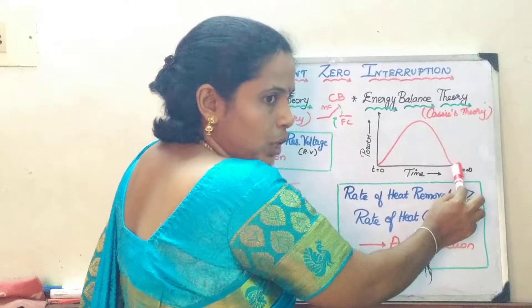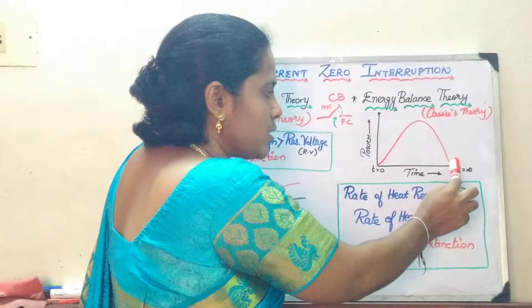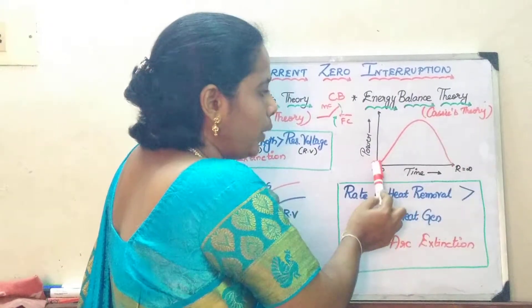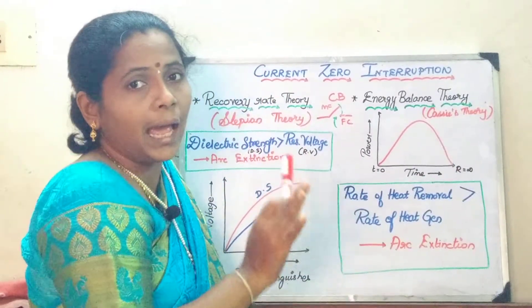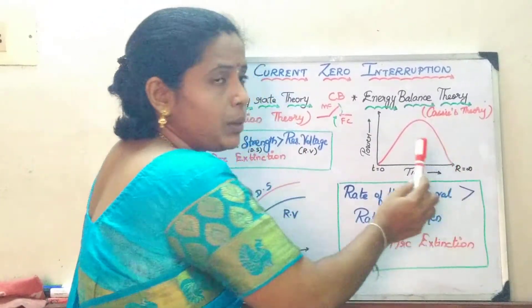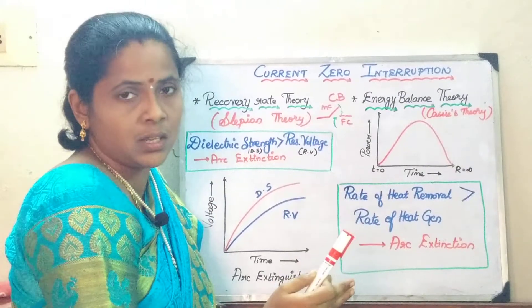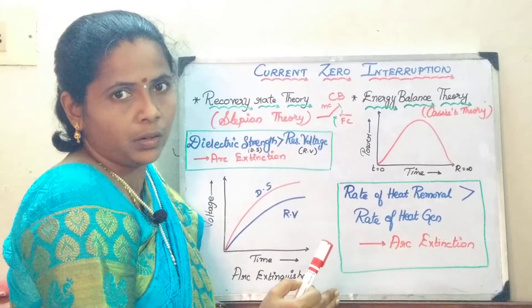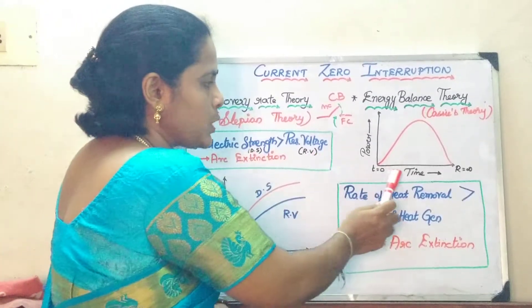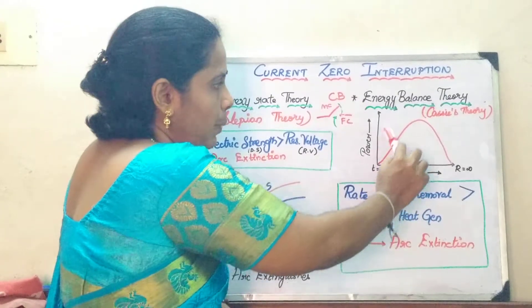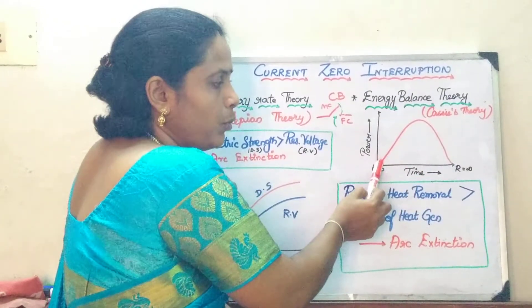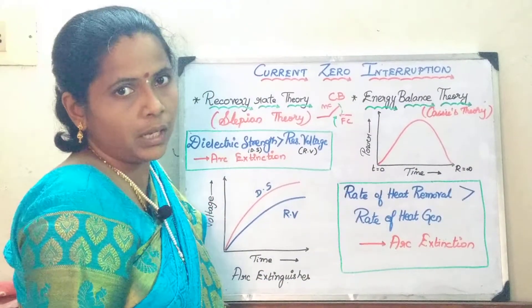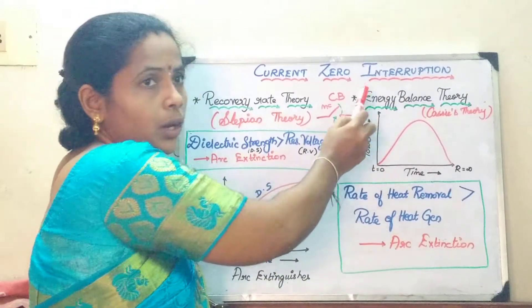This point shows the arc extinguishing process — the opening of the circuit breaker is the arc extinguishing process. Ideally, the resistance will be infinity or a high resistance, and in that case we are able to extinguish the arc in the circuit breaker. As the current and voltage increase, the power also increases. This is the starting time of opening the breaker, and this is the time at which you are going to extinguish the arc. Power multiplied by time constitutes energy.